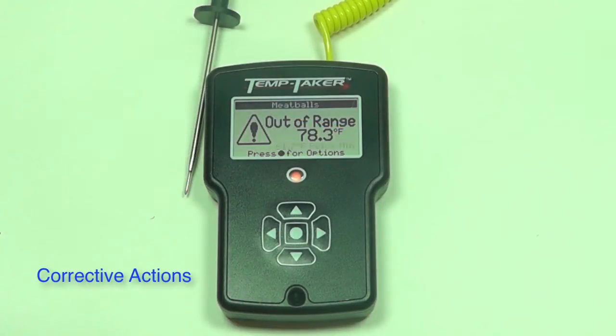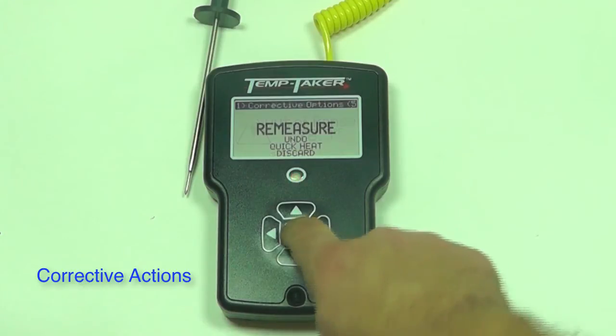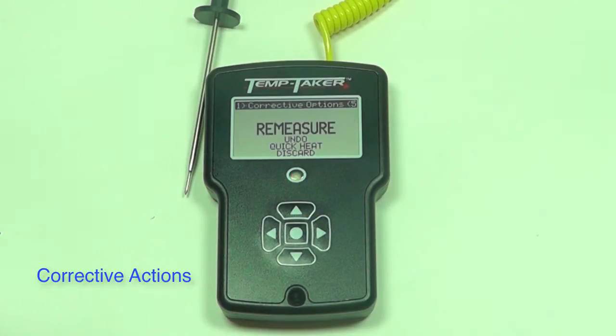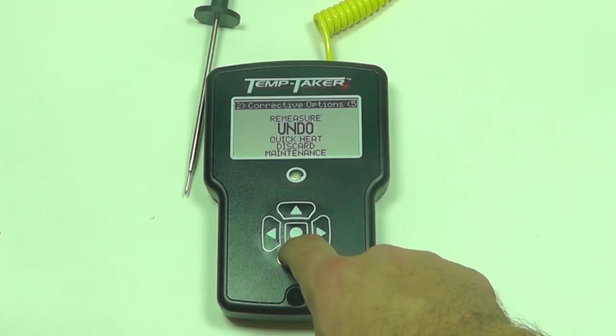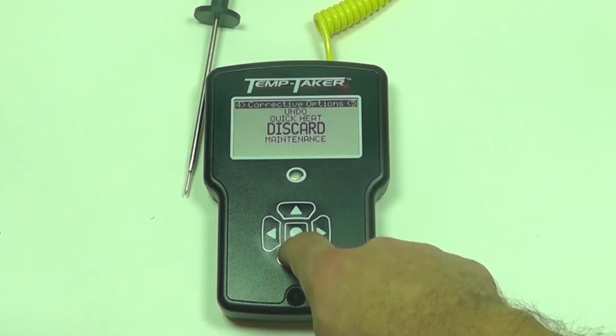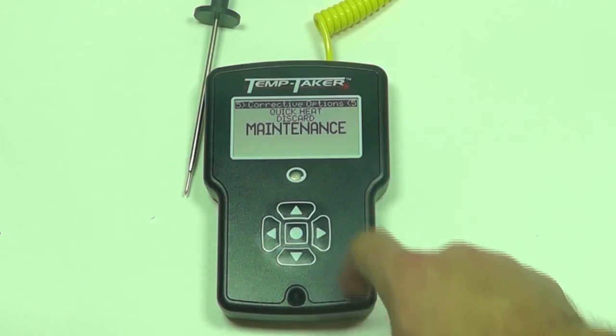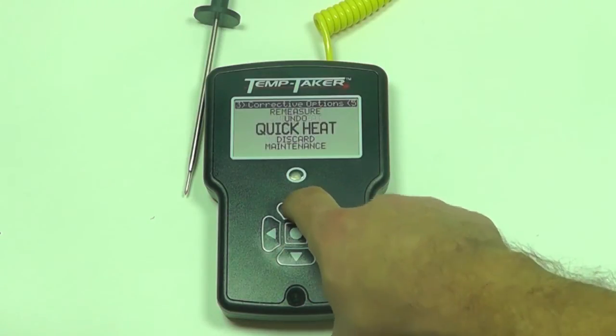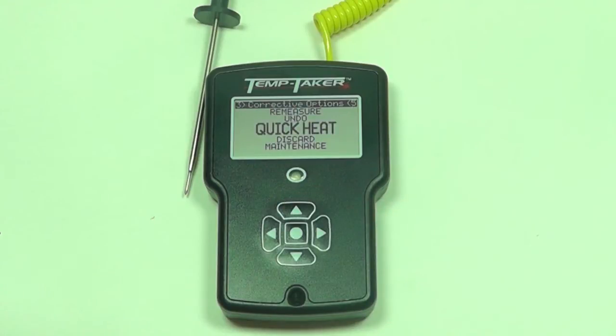By pressing the center button, the handheld then provides the user with a list of available corrective options they can choose from. They can opt to remeasure the temp again if they felt the item was not probed correctly initially, or choose from a list of additional actions complete with varying instructions. Some choices, like the option we will choose here, begin a corrective session.